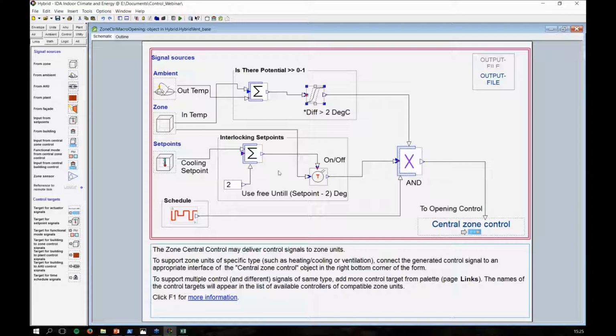So the way to decide this is I'm going to take the cooling set point from this set point module. I'm going to take the cooling set point that the mechanical ventilation has, and I'm going to leverage free cooling. I'm going to use free cooling until I reach 2 degrees below my set point. If I reach that 2 degree margin below my set point, then probably it's not enough to open the window. Then I'm going to turn it off and start my mechanical ventilation.